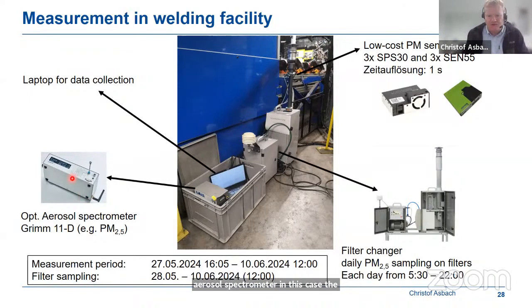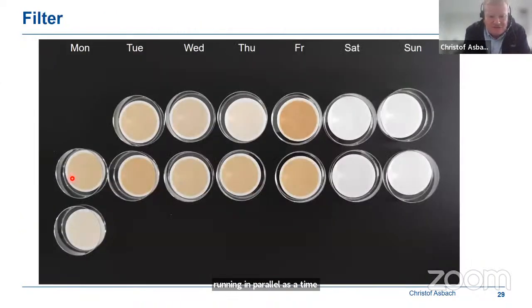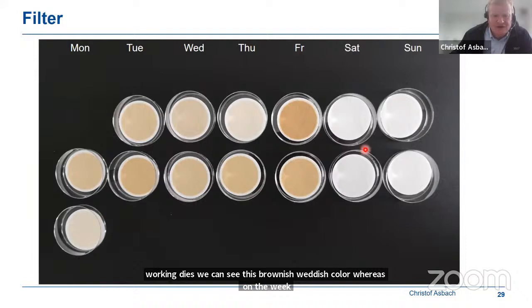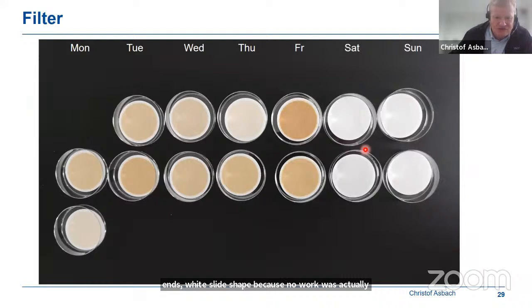We also had an optical aerosol spectrometer, in this case a Grimm 11-D, running in parallel as a time-resolved quasi-reference. Just from looking at the color of the filters, you can already see on which days the welding facility was active and people were working. On working days we see this brownish reddish color, whereas on the weekends the filters are white with a slight gray shade because no work was going on. The intention of these measurements is to eventually use the sensors to control the ventilation system on demand. If there's a high concentration, the ventilation flow would be increased, and if there's a low concentration, it would be decreased.